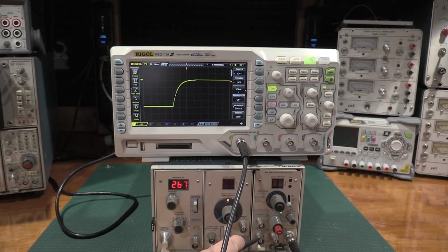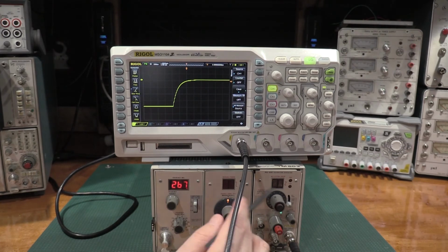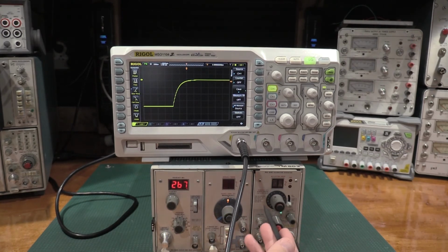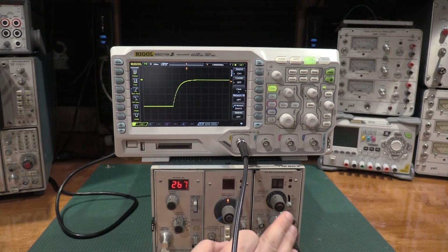To get this as accurate as possible, this is calibrated at DC. There's a switch in here, as seen in the previous video. We flip that, we go to DC. So the DMM 7510, which is the most accurate meter I have in the lab, is where this one's getting its accuracy from. Now the fast rise and fall times, 1 nanosecond will give you just about enough to calibrate a 100 megahertz oscilloscope. 1 nanosecond's plenty. These were validated on the DSA 602, the sampling scope. We have the DC accuracy from the Keithley, which was bought brand new, under cal, and I'll be sending it out for cal when it's due in, I think, February.